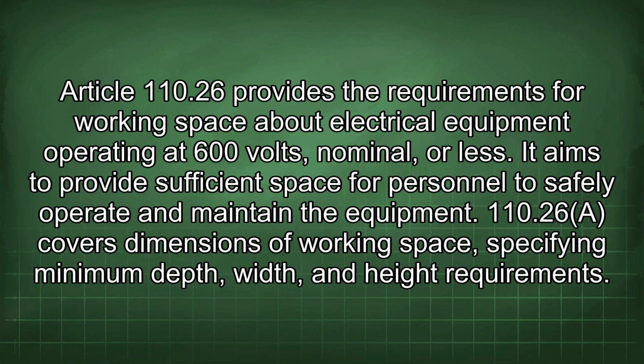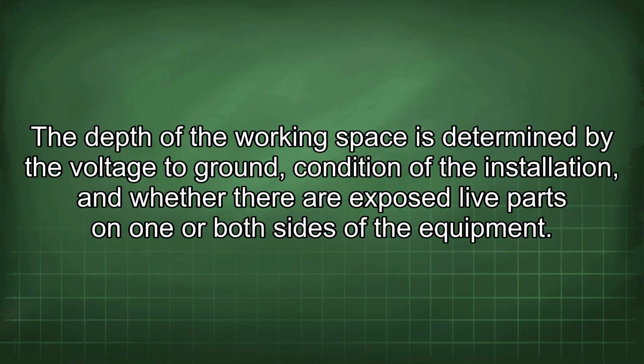Article 110.26 provides the requirements for working space about electrical equipment operating at 600 volts, nominal or less. It aims to provide sufficient space for personnel to safely operate and maintain the equipment. 110.26(A) covers dimensions of working space, specifying minimum depth, width, and height requirements. The depth of the working space is determined by the voltage to ground, condition of the installation, and whether there are exposed live parts on one or both sides of the equipment.